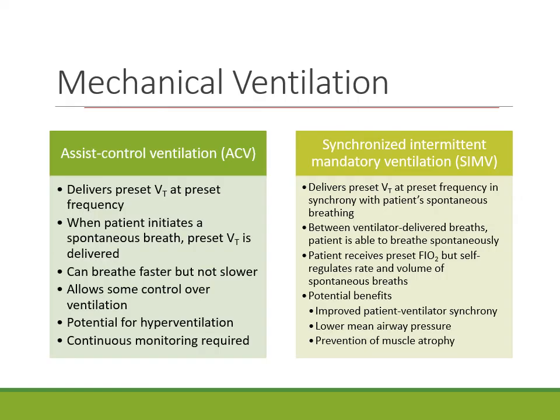respiratory drive, and ABGs. With assist control ventilation, or ACV, the ventilator delivers a preset tidal volume at a preset frequency. When the patient initiates a spontaneous breath, the preset tidal volume is delivered. The ventilator senses a decrease in intrathoracic pressure and then delivers the preset tidal volume. The patient can breathe faster than the preset rate, but not slower.